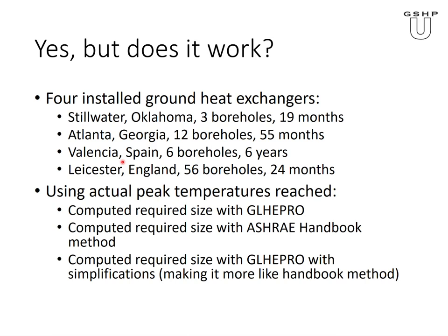Okay, so this was the work of my PhD student, James Cullen. And what we did is we tried to validate the design tool by taking these 4 systems, and for each system using the actual ground thermal properties and using the actual heating and cooling loads that were measured, going through the workflow with GLHEPRO and saying, okay, what size would this have to be? How deep would it have to be?